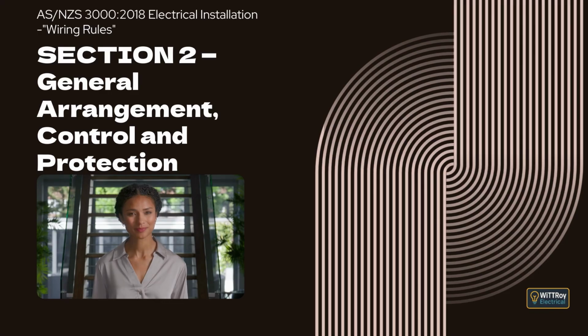2.3.3.2 General. This clause says that every electrical installation must have a main switch, located on the main switchboard, that controls the entire installation. If the installation has more than one supply, then each supply must have its own main switch on the main switchboard. There is an exception for alternative supplies such as generators or solar systems. Those main switches can be located on another switchboard, as long as they meet the product standard that applies to that kind of supply.